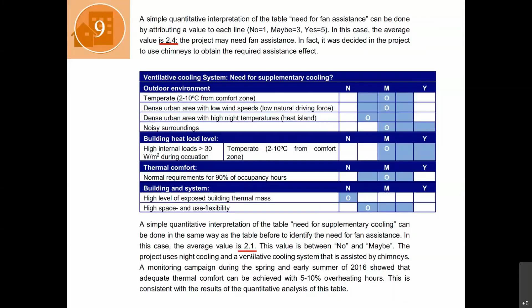When you apply these tables to that building, you get a value of 2.4 for the need for fan assistance. In fact, it's between no and yes, a maybe, which is interesting because we have the chimneys to assist the ventilative cooling system, so that's how we address this value. Then for the need for supplemental cooling, we got an average value of 2.1, again between no and maybe. In fact, we use nighttime cooling of the thermal mass as supplemental cooling to the daytime ventilative cooling system. So in general, the application of the table provides interesting, useful results.